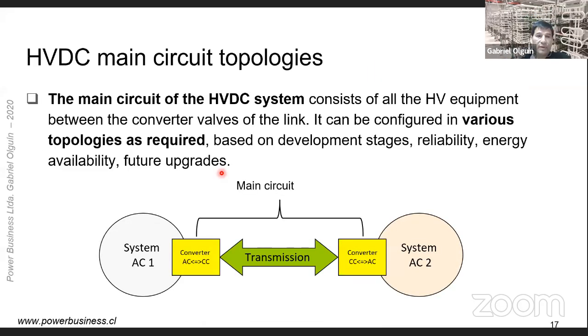So let's review the main circuit topologies. The main circuit is the high voltage DC line and high voltage DC equipment. More specifically, the main circuit of the HVDC system consists of all high voltage DC equipment between the converter valves. The main circuit can be configured in various topologies as required, based on requirements in terms of development stages, reliability, energy, etc.